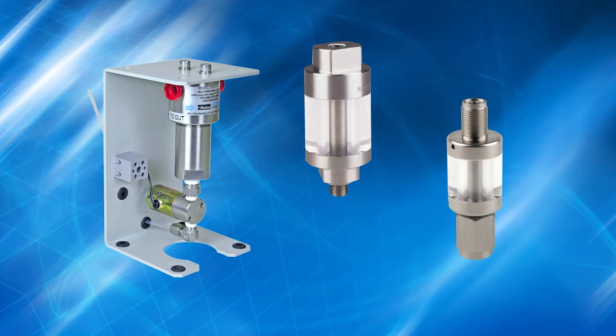Filters and liquid traps are often used to prevent damage from contamination, but they can't stop all of it from returning to the calibrator, especially the airborne vapors common when you depressurize a vessel.